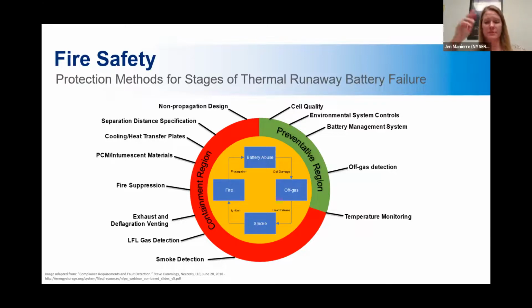So I mentioned the first time you saw this chart, when it didn't have all of this wonderful information sticking off of it, that's what would happen if a battery is abused and there were no checks in place, right? But as you follow this around again now, from the 12 o'clock point all the way around, these are all of the checks and balances and safety features that will be in place for these systems based on the fire code. So all of these controls are essentially addressed in the chapter of the fire code in some way, shape, or form.